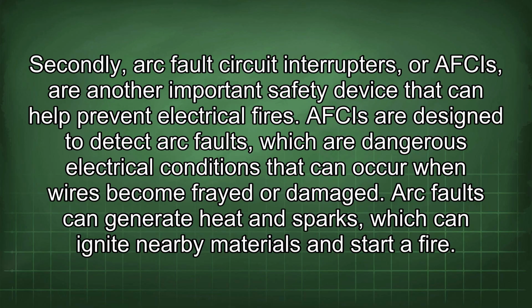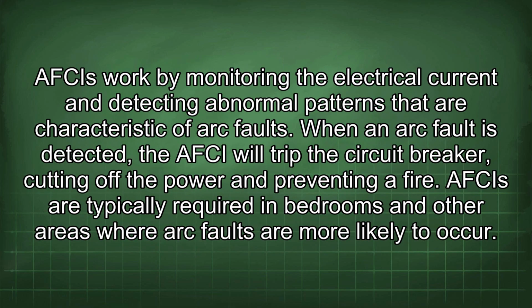Secondly, arc fault circuit interrupters, or AFCIs, are another important safety device that can help prevent electrical fires. AFCIs are designed to detect arc faults, which are dangerous electrical conditions that can occur when wires become frayed or damaged. Arc faults can generate heat and sparks, which can ignite nearby materials and start a fire. AFCIs work by monitoring the electrical current and detecting abnormal patterns that are characteristic of arc faults. When an arc fault is detected, the AFCI will trip the circuit breaker, cutting off the power and preventing a fire. AFCIs are typically required in bedrooms and other areas where arc faults are more likely to occur.